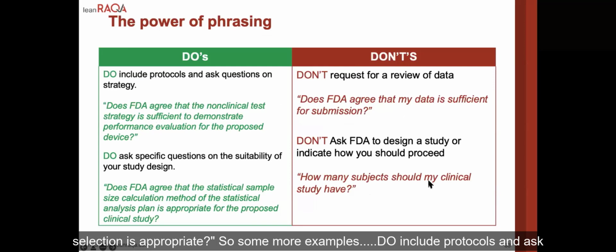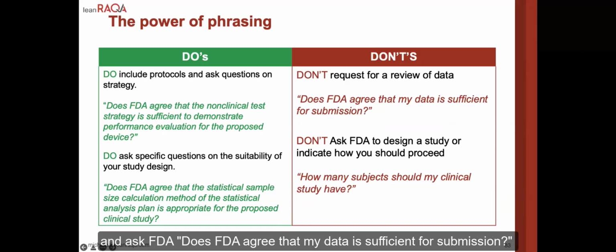So, some more examples. Do include protocols and ask questions on strategy. So does FDA agree that the non-clinical test strategy is sufficient to determine performance evaluation for the proposed device? But don't request review of data. So don't have already run a protocol and then turn the data in for review and ask FDA, does FDA agree that my data is sufficient for submission?